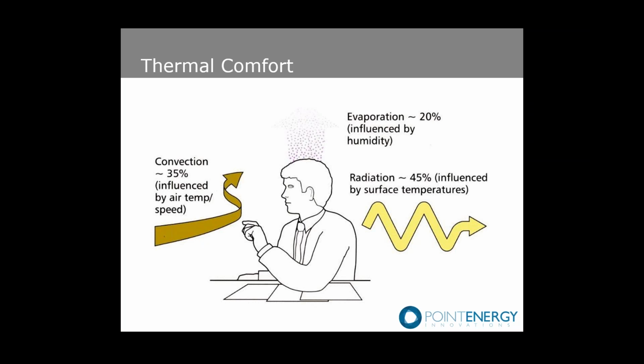Thermal comfort is influenced by several different things: convection, which is air temperature as well as air speed—if you turn on a fan, you feel a little more comfortable, that's convection; evaporation, which is sweating and losing heat via evaporation, influenced by relative humidity in the space; and radiation, since you're a warm body radiating, in most cases, to cooler surfaces around you. If the building structure is warm, it's actually radiating heat to you. All three components are important for HVAC systems, because our ultimate goal is thermal comfort, and our secondary goal is delivering that comfort with extremely high energy efficiency.